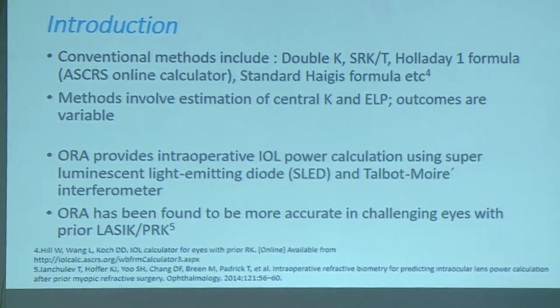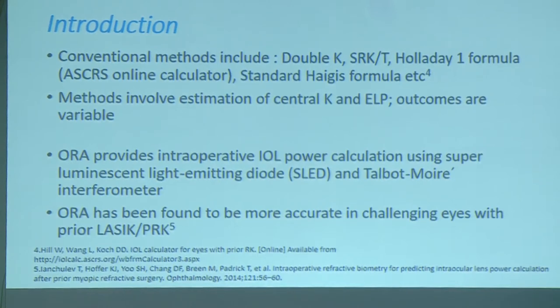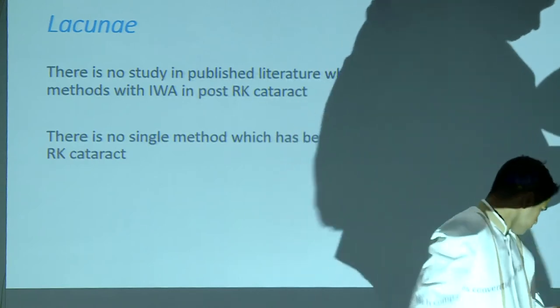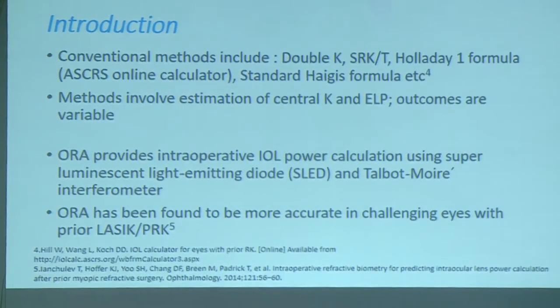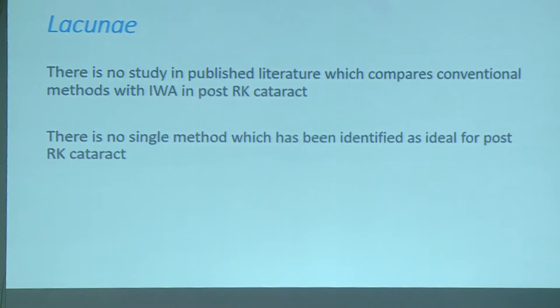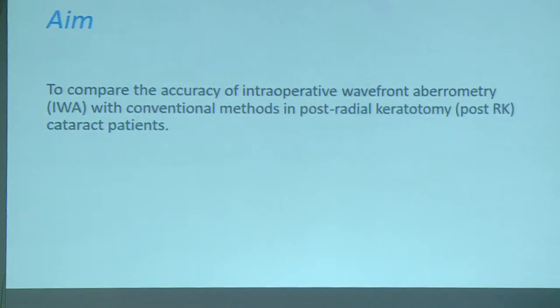Conventional methods for IOL power calculation include the double-K method, SRKT, Holladay 1 with ASCRS online calculator, and standard Haigis formula. These methods involve estimation of central K and ELP and outcomes are variable. ORA — Optiwave Refractive Analysis — provides intraoperative IOL power calculation using a SLED superluminescent light-emitting diode system and Talbot-Moiré interferometry, generating fringe patterns to find sphere, cylinder, and axis. It has been found more accurate in challenging eyes such as prior LASIK and PRK, but there is no published literature comparing conventional methods with intraoperative aberrometry in post-RK eyes.